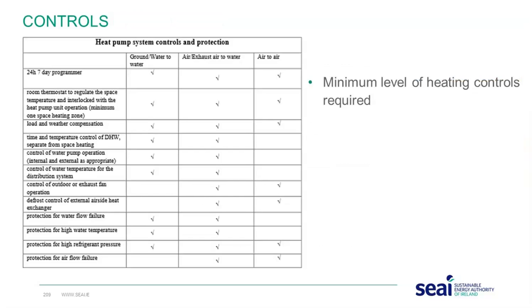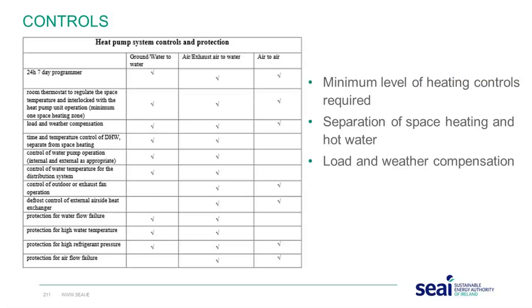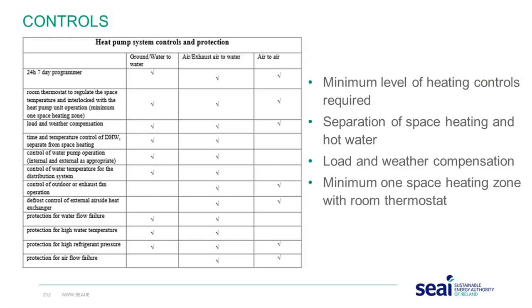In relation to controls, SEAI, as part of the domestic technical standards and specifications, set out the minimum level of controls. You can take them from the table here. I won't go through them one by one. Some really important parts: separation of space heating and hot water is essential, as are load and weather compensation. And there must be a minimum of one space heating zone with one room thermostat. It cannot rely solely on load and weather compensation alone.